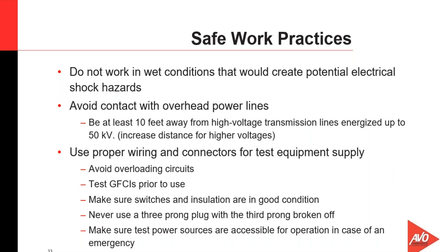Making sure we have adequate power to feed our test equipment is also an issue, and again, the use of GFCIs is a good idea. We'll make sure switches, if we're using switches or ancillary equipment, make sure these pieces of equipment have been inspected. If they're grounded equipment, then we have the third prong, ground prong there available.